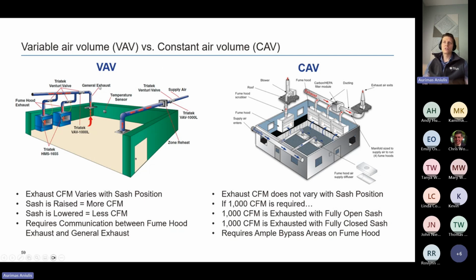While variable air volume systems allow you to throttle the exhaust down in unoccupied or unused modes, the sequence of operations in VAV applications is a lot more complex, because you need to define occupancy, you need to define setback modes for low air changes and occupied air changes, and potentially even contaminant levels if we're doing air quality type metrics. Now, when it comes to constant air volume systems, I call it a set-it-and-forget-it design, because the moment you get all your CFMs right, you lock it in place and you forget it. What this does is simplify the design front end, but it locks the users into a fixed exhaust, a fixed cost of running that lab, with very few opportunities to increase efficiency so they can decrease their utility bills.